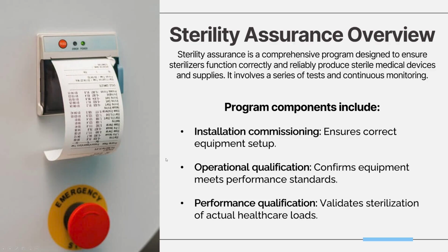So, sterility assurance overview. It's a system that confirms devices are reliably sterilized. It includes installation commissioning, so you ask questions like, is this equipment installed correctly? And we also have operational qualification. So does it work according to specification?